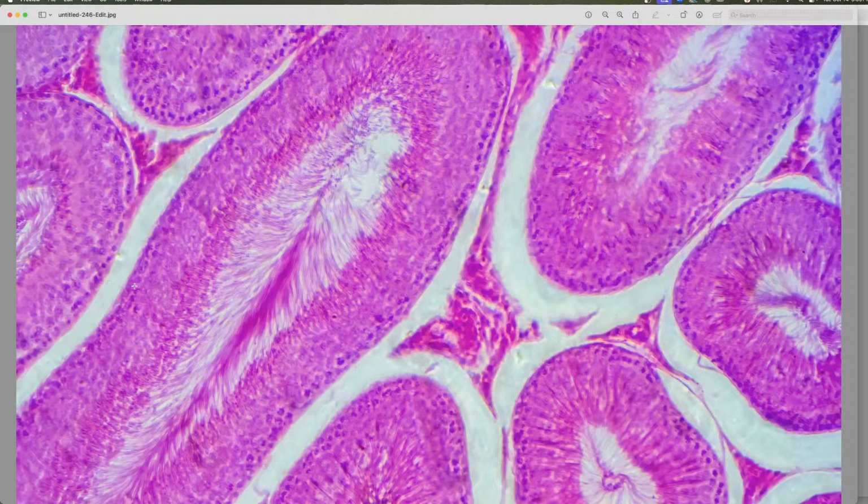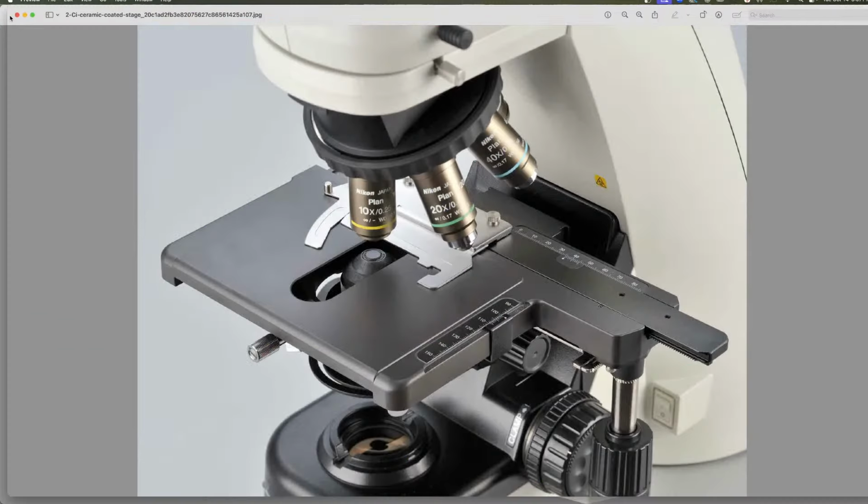So typically these microscopes are made for this. They are made for looking at objects with transmitted light. The metallurgical objectives that we like to use are designed to use reflected light and allow us to get a much more three-dimensional sense of our subject. You can also do this with these microscopes. It's not too much problem, especially if you're working with objectives that give you some decent working distance. These don't, by the way. The working distance on these things is very, very limited, especially as the magnification goes up.